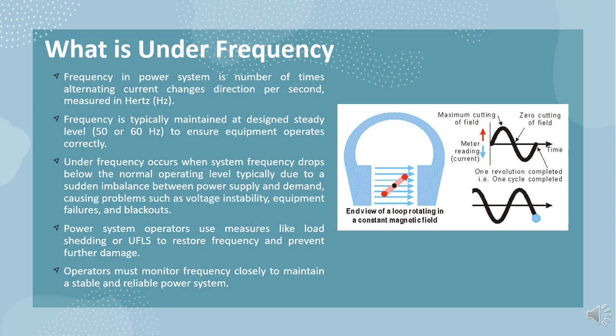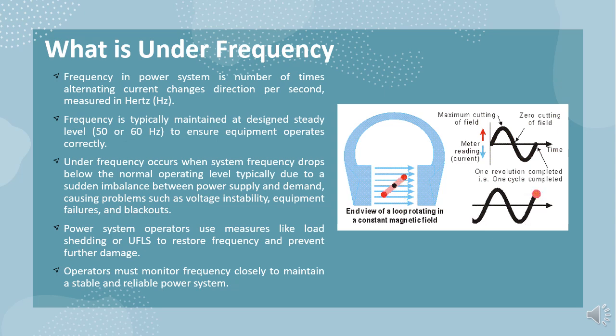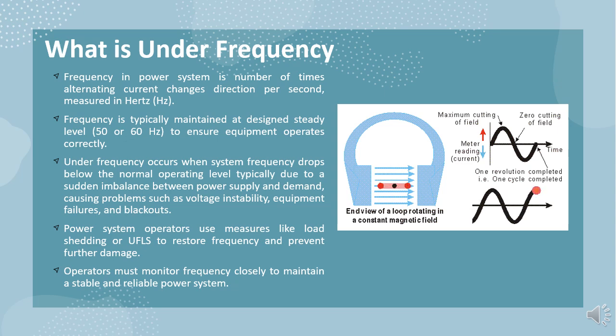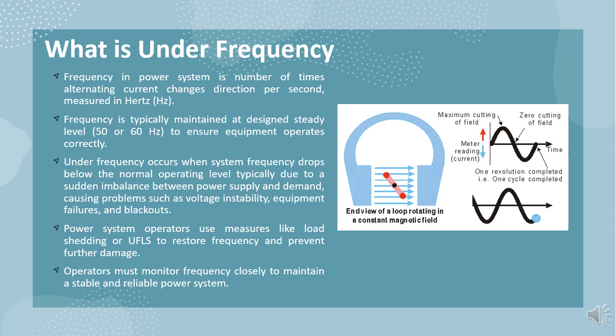To restore frequency and prevent further damage, power system operators use measures like load shedding or under-frequency load shedding (UFLS). Load shedding involves the intentional reduction of power to a section of the power grid, while UFLS is a more automated process that involves disconnecting certain loads to restore frequency. It's important for power system operators to monitor frequency closely to maintain a stable and reliable power system. In summary, under-frequency occurs when the power system frequency drops below the normal operating level due to an imbalance between power supply and demand. Power system operators use measures like load shedding and UFLS to restore frequency and prevent further damage.